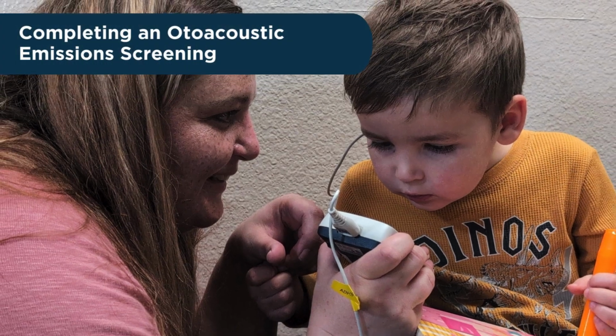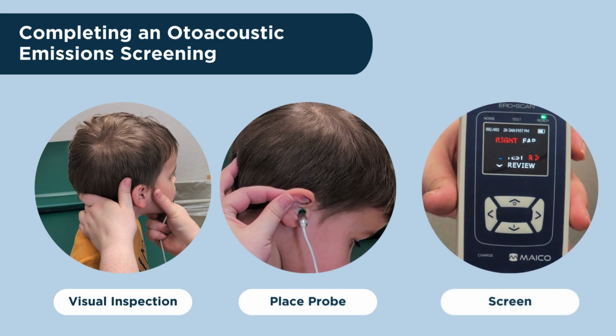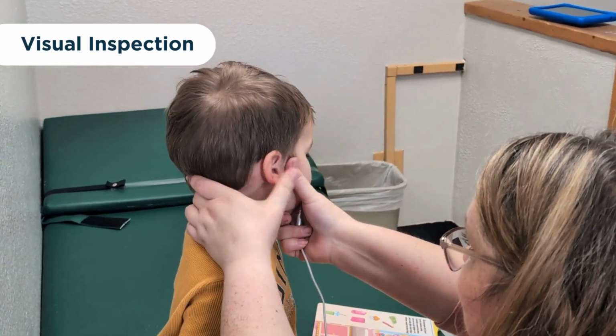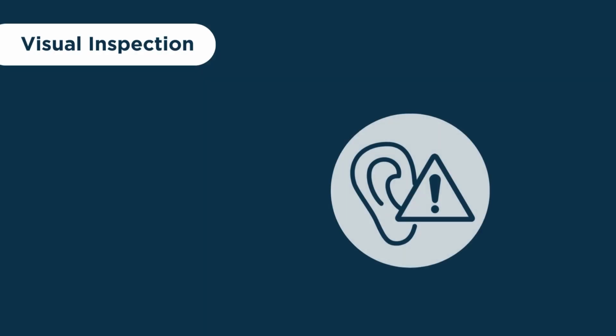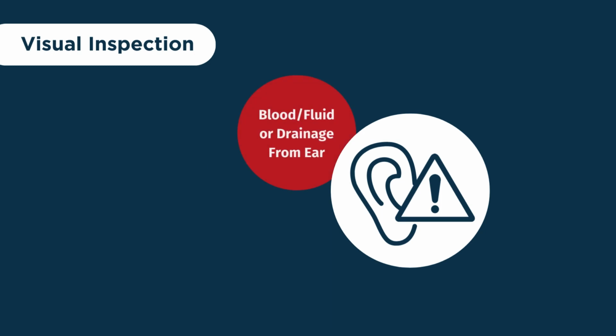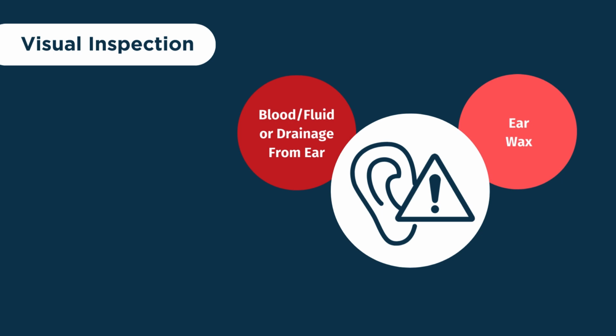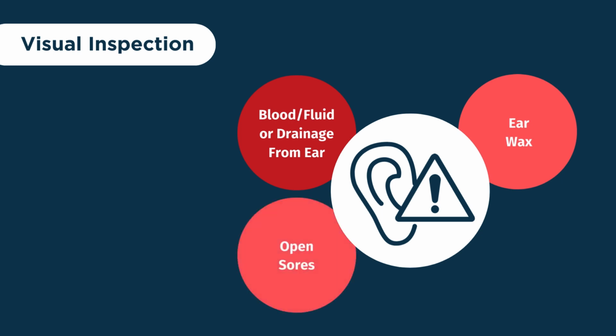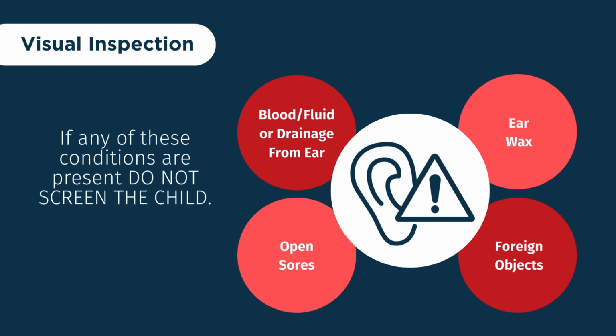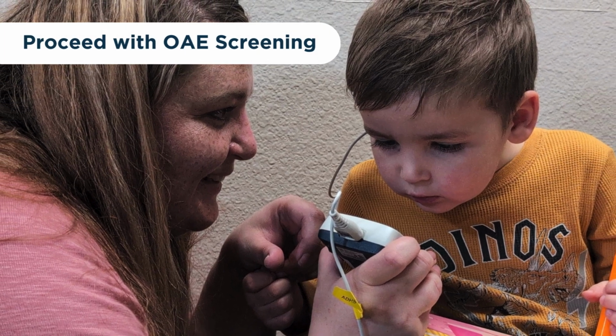We will now walk through the otoacoustic emissions (OAE) screening process step by step. First, we'll do a visual inspection of the ear. As a reminder, the 4 reasons not to screen listed in Arizona's hearing rules are blood, fluid, or drainage from the ear, earwax that may be occluding or blocking the ear canal, open sores on the ear, or a foreign object in the ear canal. If any of these conditions are present, the child should not be screened and their parent or guardian should be notified as soon as possible. If ears appear healthy, proceed with the OAE screening.